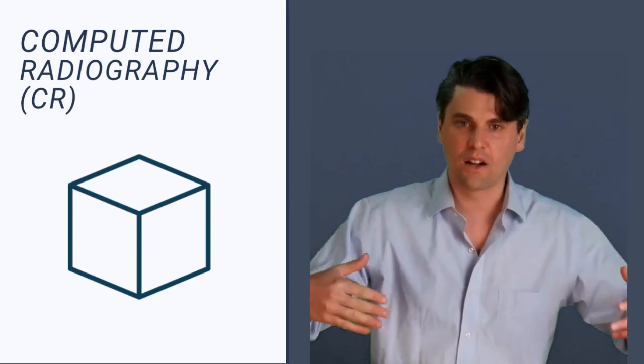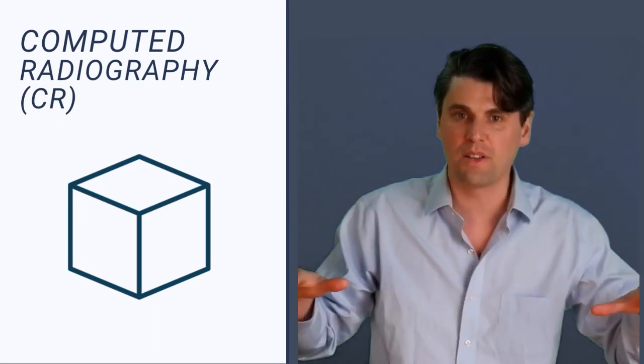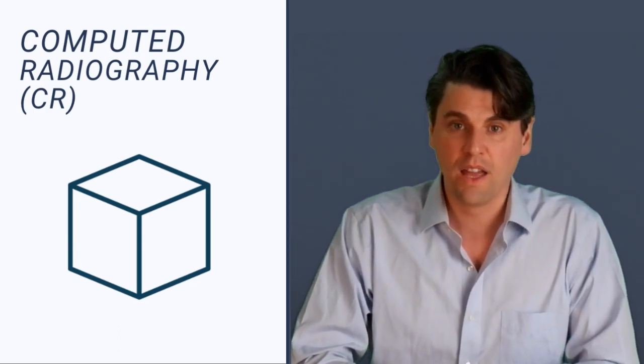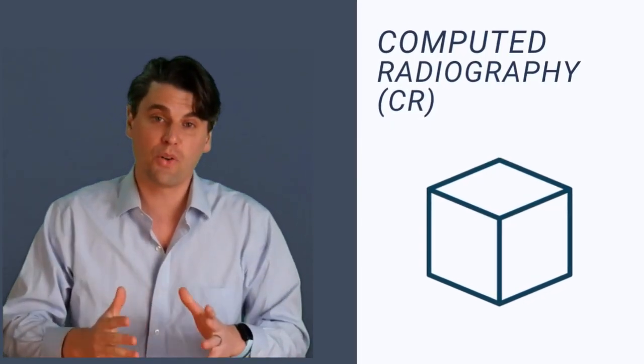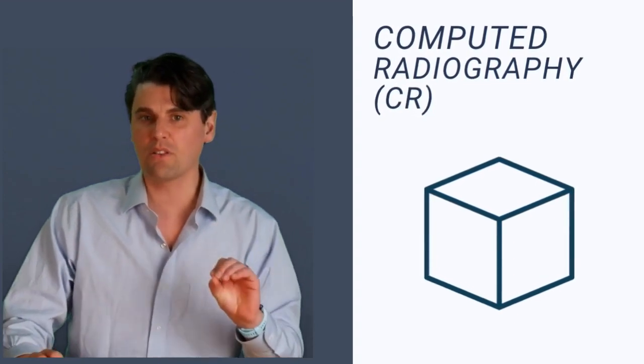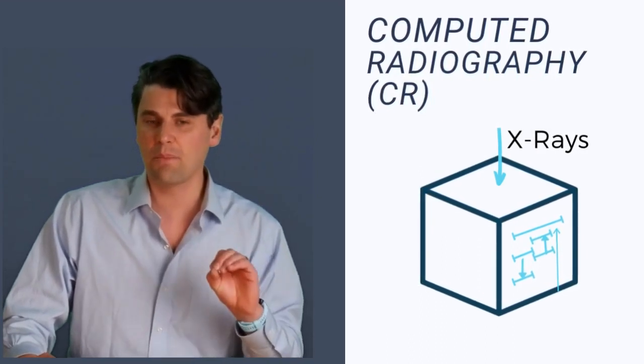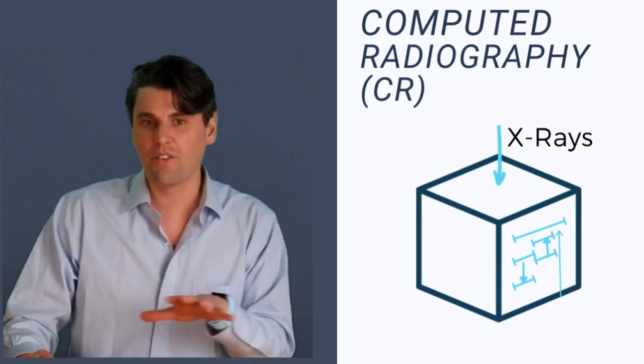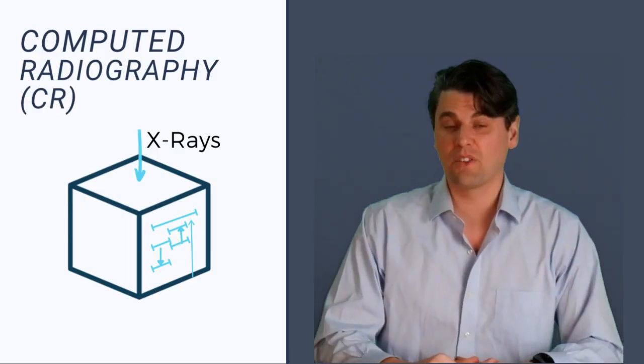You want to make it totally flat field such that there are no remnants of the previous acquisition. Now I'm going to go through computed radiography in a couple of steps. I'll draw just a flat sheet, which is our material. The computed radiography material is what we call a photoluminescent phosphor — for instance, barium fluoride bromide. This is a special type of material such that we can have x-rays incident on that material, and then some energy is stored in the material. That's why we call it a latent image — it's inside the actual material, but we can't see it with our eyes. On the photo-stimulated luminescent material, the latent image is proportional to the x-ray exposure incident on that material.